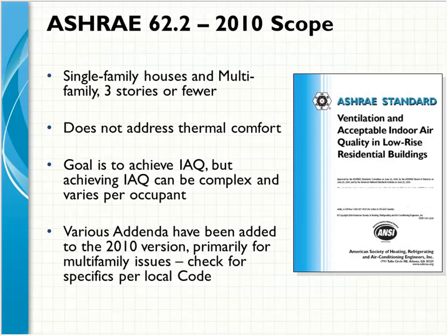All right. And if I could interject real quick, we verify a lot of homes, and even in states without codes where you need to test this equipment, if folks are using LEED or Green Star or National Green Communities, there's extra credit for the testing, but it's not required. But we would say that if you're hiring a contractor or a rater, that's something they should just be doing. Get that extra credit, because a lot of times we see, unfortunately, in real projects, when they go to test the system, typically there is something wrong, and it just needs a slight adjustment. So, I just want to second that and highly encourage that.